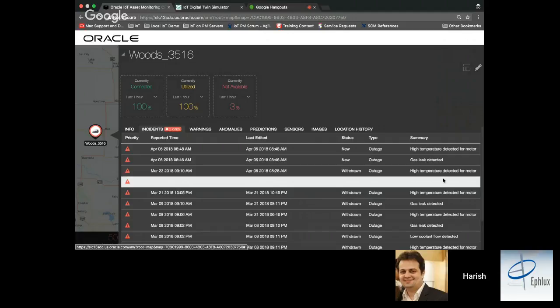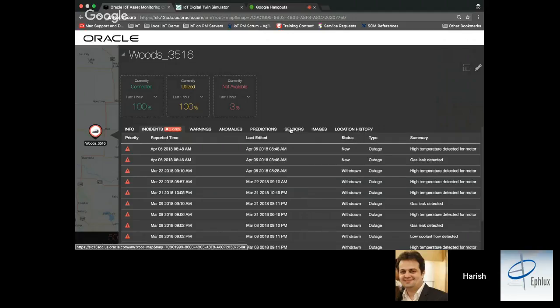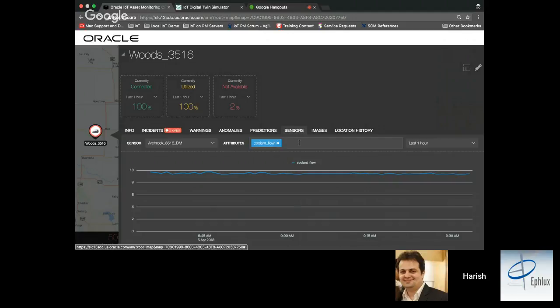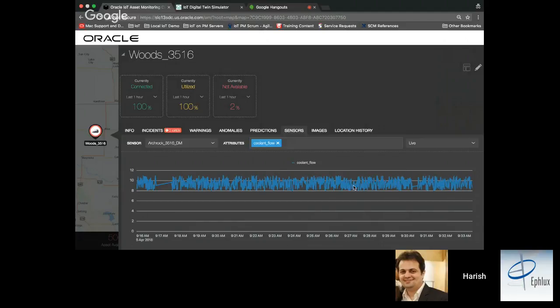So something is going wrong with this equipment, which requires action. Now let me briefly tell you how this incident was created, what's happening in the background. Typically these compressors have a variety of different sensors attached to them, measuring different environmental and health parameters of the equipment. For example, I have a sensor which measures the coolant flow, and I can see in real time how that coolant flow is fluctuating.